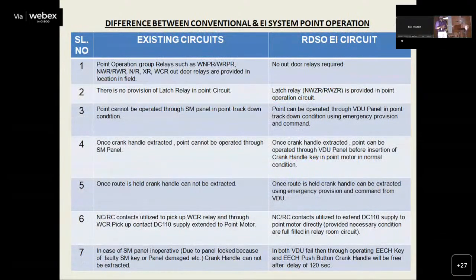First we discuss the difference between the old conventional system and the standardized system we now use. Previously, point group relays were available at the signal location, and the 110V supply and other functions were extended using those relays available at location. But in the present system there is no relay at the outdoor location - the 110V supply is directly extended from the power room, from the relay room itself, through multi-core cable to the signal location to operate the point.